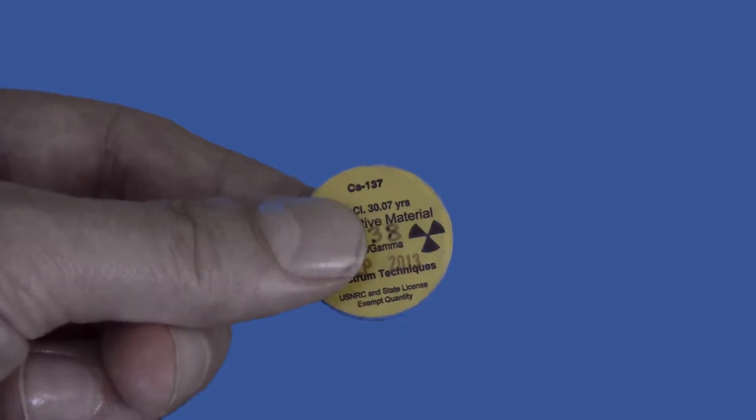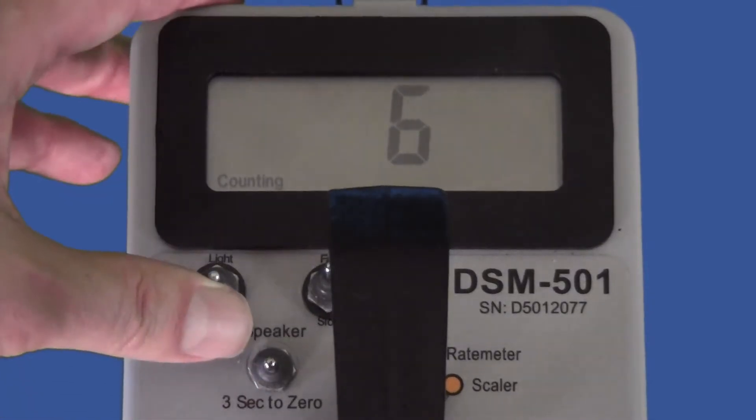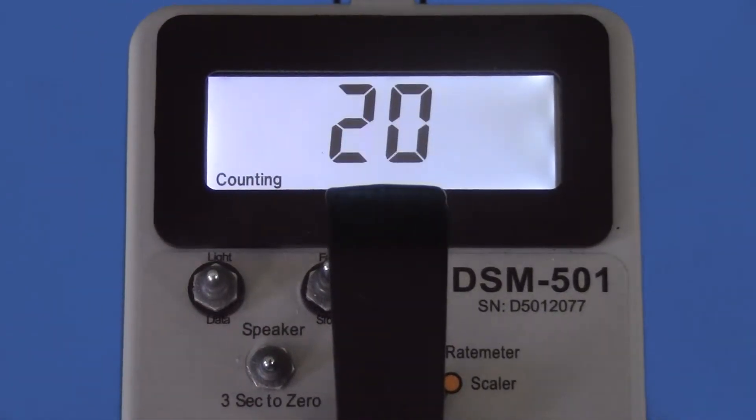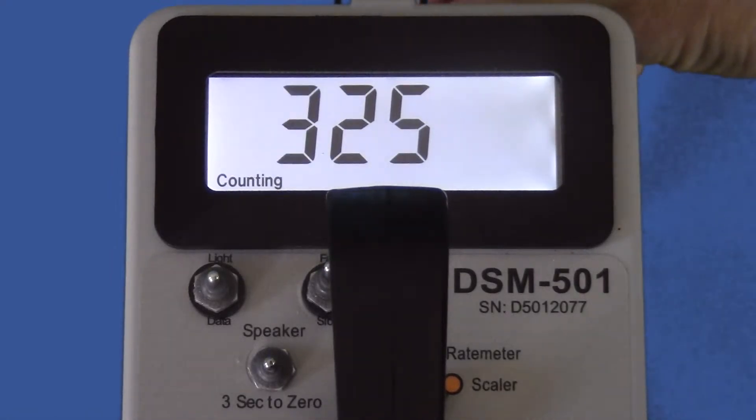We will test the scaler mode using a 1 microcurie cesium-137 check source. First, turn to scaler mode. Place the source near the detector window. As the scaler counts to 10 seconds, we wait. The reading is 1,287 counts.